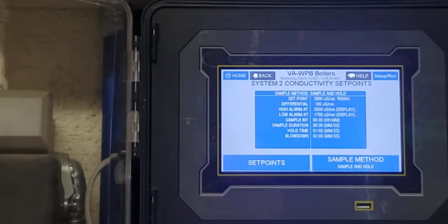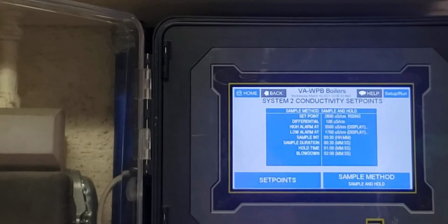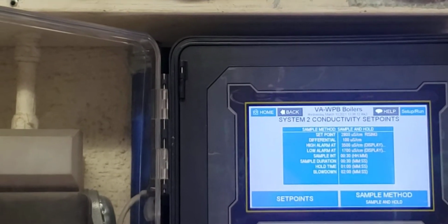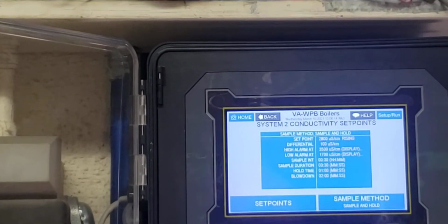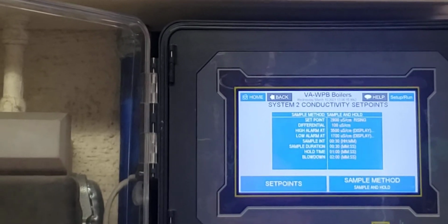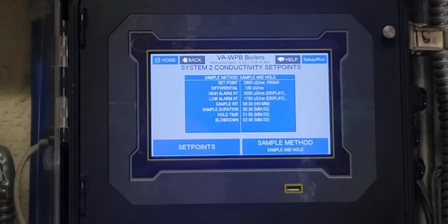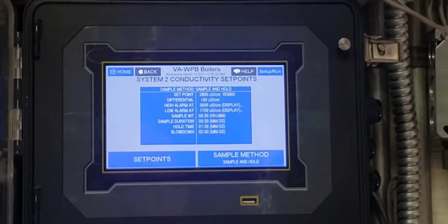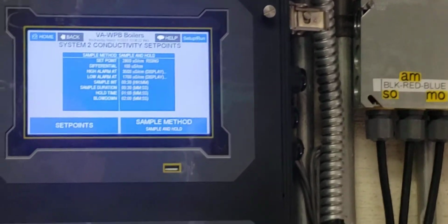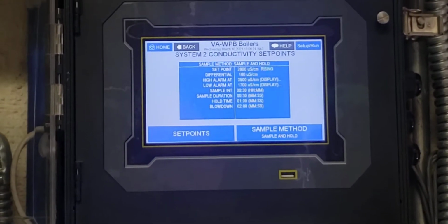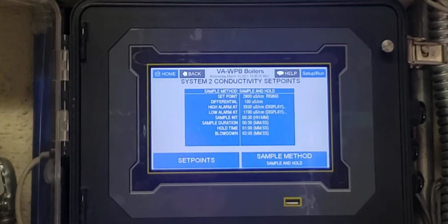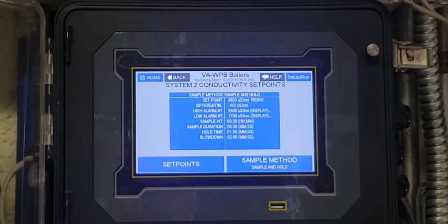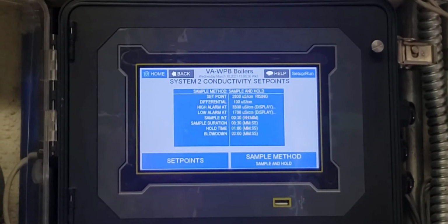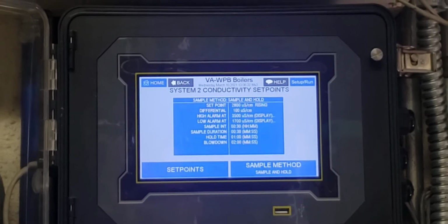Yeah. So I changed the other one to a longer wait, where they had to wait 15 minutes, and then it only sampled for a smaller blowdown time. And then I wanted to see if that helped, if that kept us up with the logs. It was just an experimental thing, because I know we're just setting this thing up to run right. You think the 30-minute hold was good on boiler 2?